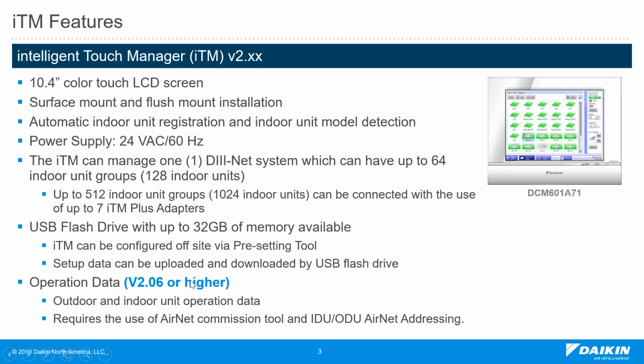Starting from version 2.06, we added the operation data of the outdoor unit, and all the sensors of the indoor unit can be saved and stored in the ITM. After that, the user can download it over a web browser or USB drive. This function was added from version 2.06, and it requires the AirNet engineering tool and commissioning. We did another webinar before on how to use the AirNet commissioning to enable the operation data.